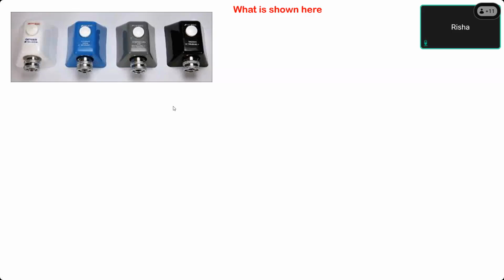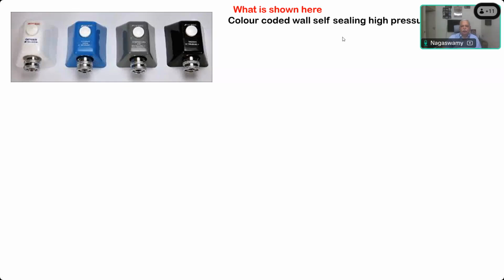No, sir. We have a check valve. Now, is it called check valve or some other valve? Self-sealing valve, sir. Self-sealing valve, very good. It's called color-coded wall-mounted self-sealing high-pressure gas outlets, also known as Schrader valves. Okay, so that is the thing that has been noted.